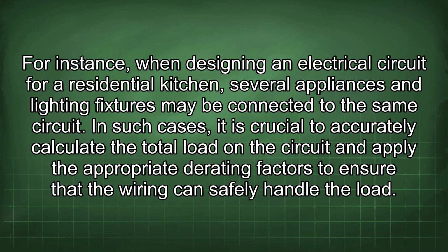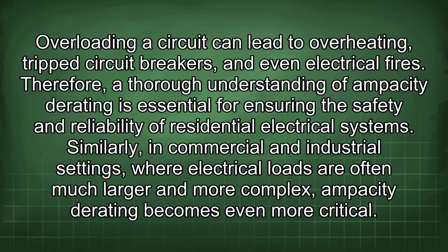For instance, when designing an electrical circuit for a residential kitchen, several appliances and lighting fixtures may be connected to the same circuit. In such cases, it is crucial to accurately calculate the total load on the circuit and apply the appropriate derating factors to ensure that the wiring can safely handle the load. Overloading a circuit can lead to overheating, tripped circuit breakers, and even electrical fires. Therefore, a thorough understanding of ampacity derating is essential for ensuring the safety and reliability of residential electrical systems.